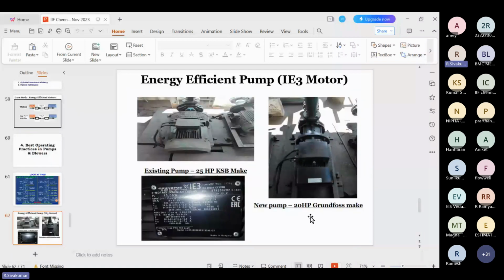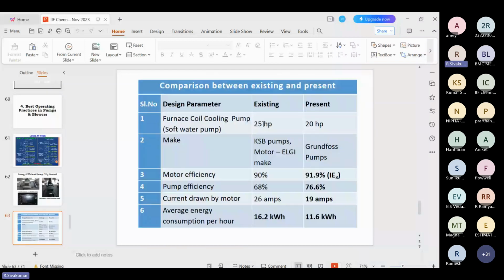So this pump example: at one of the leading foundries in Coimbatore, we replaced the coil cooling pump with an energy efficient Grundfos pump. The old pump was 25 HP. The new Grundfos pump was 20 HP. From 25 HP to 20 HP, we changed to an energy efficient IE3 motor. The nameplate itself shows IE3. So the existing pump capacity is 25 and the present is 20 HP. Motor efficiency is 90, here 91.9, IE3 standard.